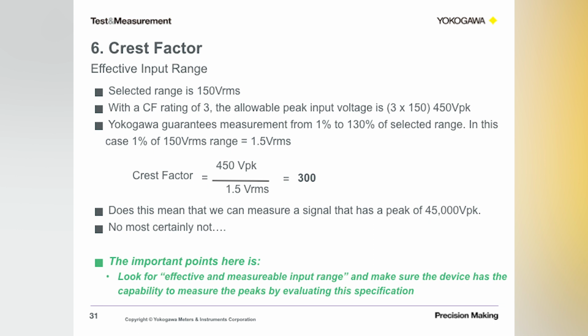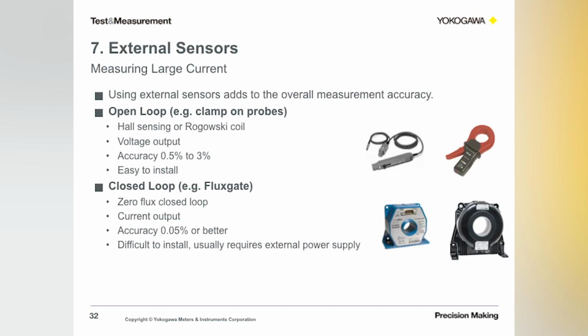So the bottom line is, you don't want your signals to be clipped off because it will affect your overall power calculations. A good power meter or analyzer should have the capability to measure those peaks and provide accurate measurements. So, what other factors could affect uncertainty of your measurements? External sensors. Anyone out here use external sensors to measure large currents? I'm sure you have. I've known many customers who resort to that.